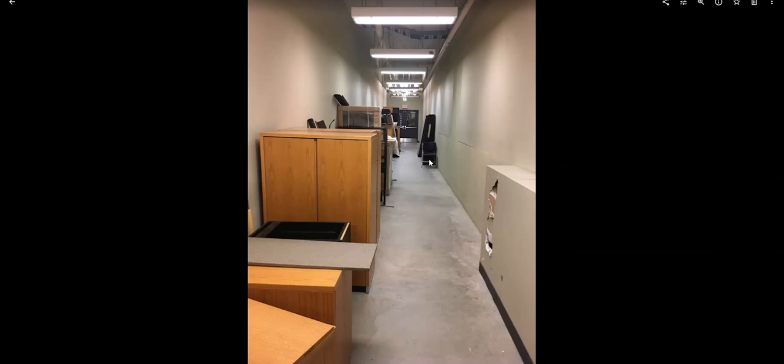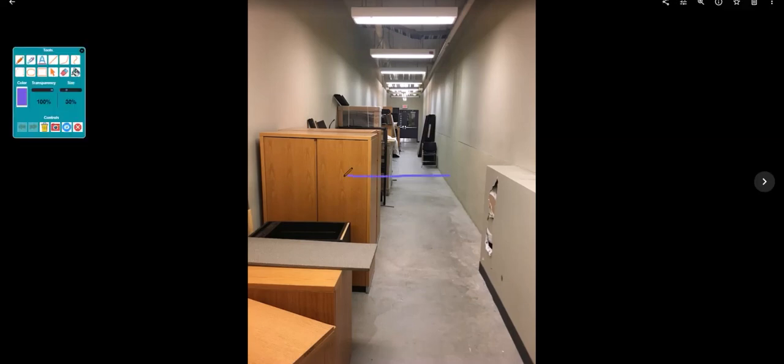So once I saw that, I immediately phoned the operations people of this building and said, you need to get that cleaned out. The width of this corridor is 100% based on the amount of people coming down that stair and entering from the lower floor as well into that stair or into that corridor. And now this is just looking down the other part of the corridor. So now this is a long corridor that heads to the exterior. Again, the width of this corridor was based on an occupant load, and they're storing stuff in there. So I phoned the operations people and I explained the situation to them.